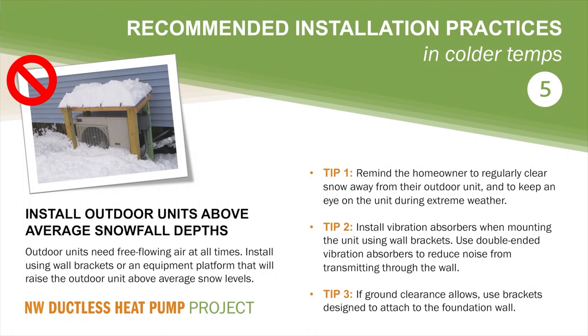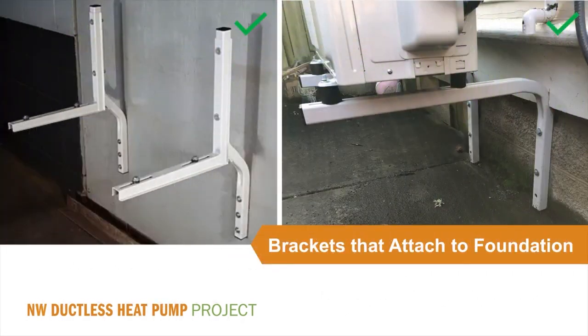Tip number 2 includes installing vibration absorbers when mounting the unit using wall brackets. Especially use double-ended vibration absorbers to reduce noise from transmitting through the wall. Tip number 3 is, if ground clearance allows, use brackets designed to attach to the foundation wall, as these have been found to transmit little or no noise and vibration through the structure. Here you will see several examples of wall brackets that are designed to attach to the foundation wall. This style of wall bracket has been designed to reduce or eliminate any sound or vibration being transmitted through the structure.